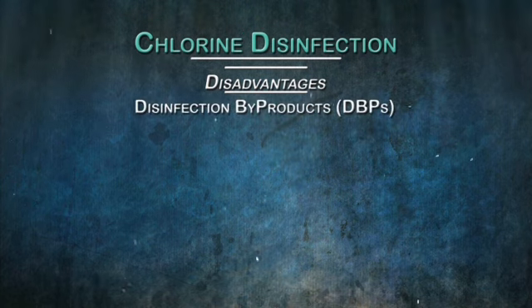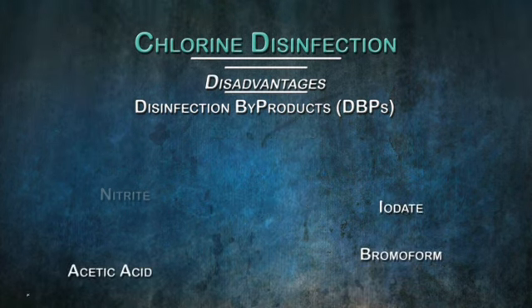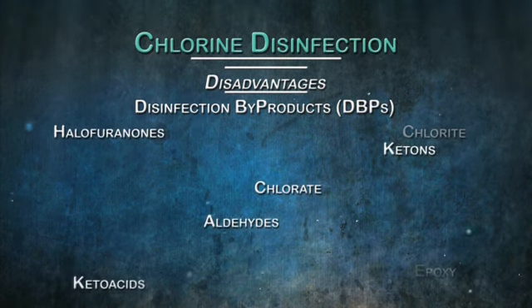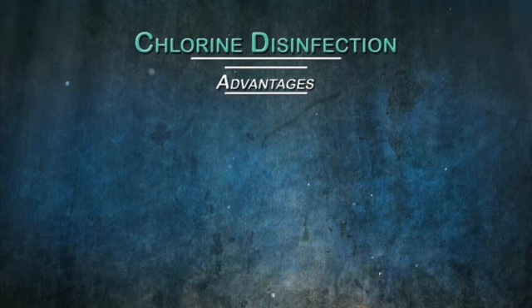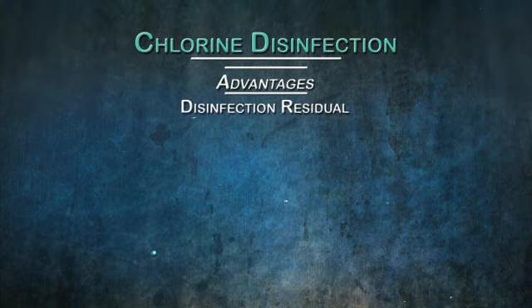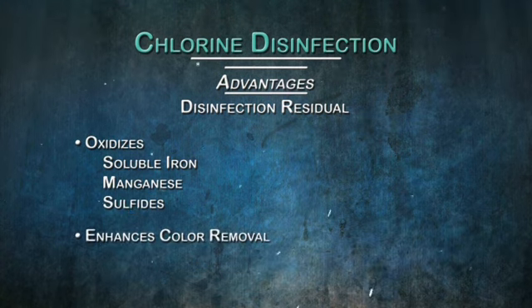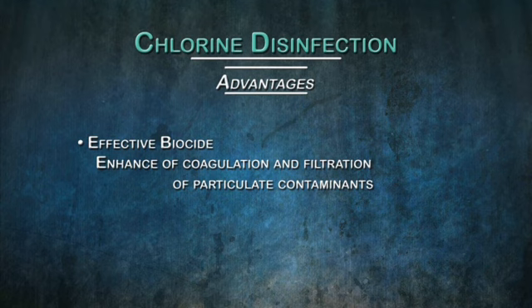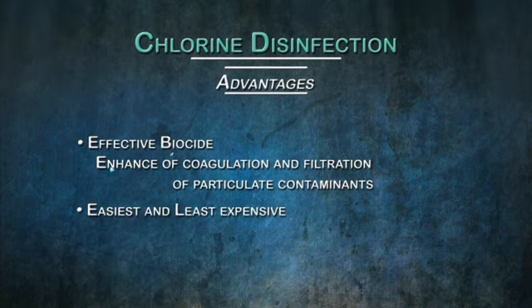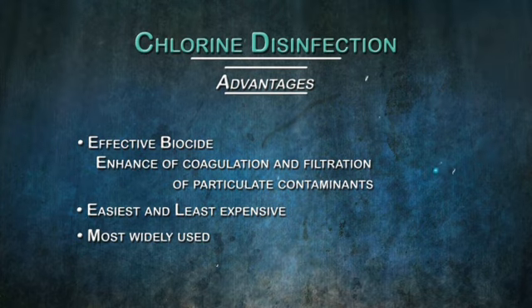One disadvantage of disinfection by free chlorine, especially with surface water systems, is the potential for the formation of disinfection byproducts, or DBPs. For example, halogenated organics are formed when natural organic matter, NOM, reacts with free chlorine. Total trihalomethanes and haloacetic acids are common disinfection byproducts. However, the use of chlorine has numerous advantages in addition to producing a disinfectant residual, such as it oxidizes soluble iron, manganese, and sulfides, enhances color removal, and can reduce overall taste and color. Other advantages include the enhancement of coagulation and filtration of particulate contaminants, as it acts as an effective biocide, and is the easiest and least expensive disinfection method, regardless of system size. It is the most widely used disinfection method, and therefore, the best known.